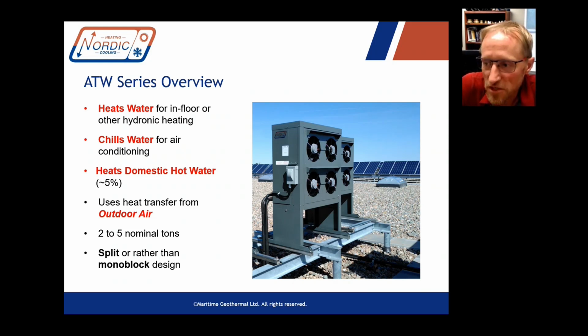Gotcha. So okay, it is switching back and forth, and you can set the priority. If there's simultaneous demands, you can have it do the cooling first or the heating first. Okay, but it's not a waste heat process. Like you're still rejecting the... Yeah. Okay. Yeah. Air source heat pumps aren't as flexible as water to water heat pumps. It is more complicated, but you can do simultaneous heating and cooling with a water to water heat pump, and that's something that we can also give advice on.